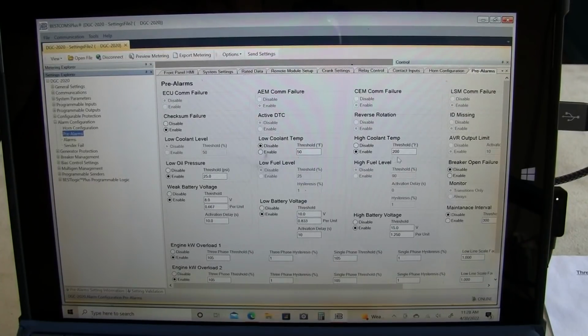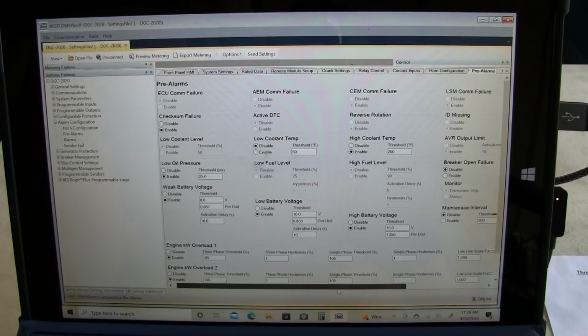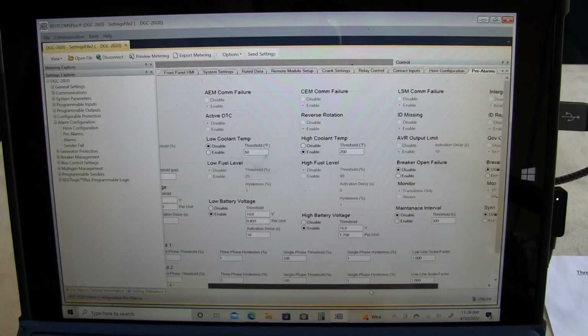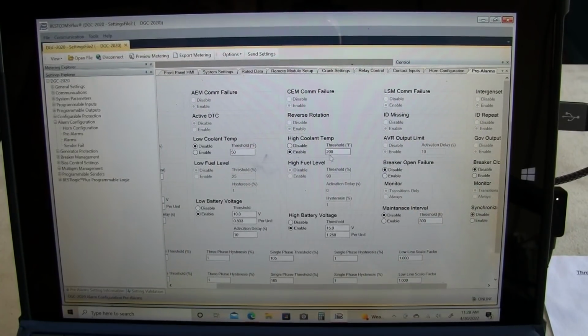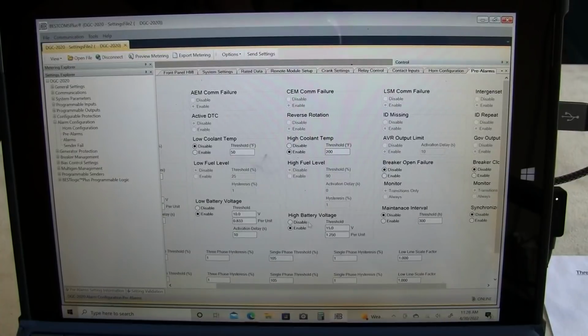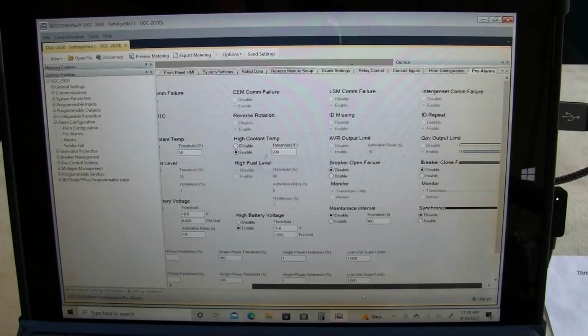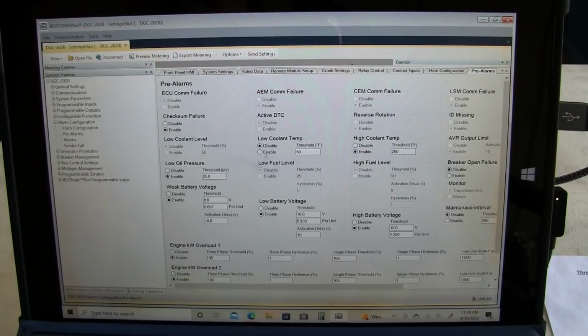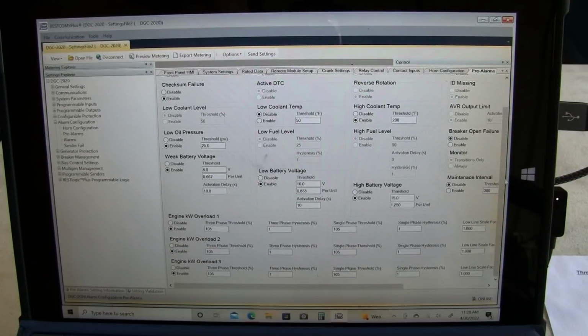High coolant temp is enabled. Move over a little bit here. So pre-alarm for high coolant temp is set at 200 degrees. If the unit hits 200 degrees, the alarm will sound. The unit will keep running though. High battery voltage, 15 volts, in case the alternator starts overcharging. Let's see, what else? And overload, engine kilowatt overload is 105%. So if our load exceeds 105% of the unit's rating, we'll trip pre-alarm.